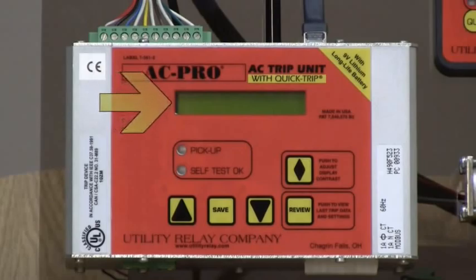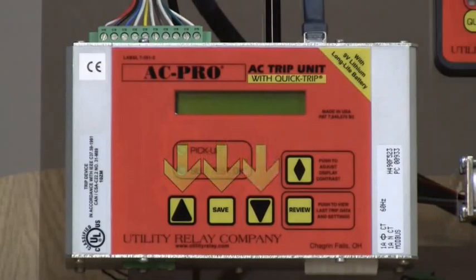The AC Pro has a 16-character liquid crystal display with a backlight. The contrast button is used to adjust the LCD contrast. Just push and hold the contrast button until the desired contrast is reached. When the contrast button is released, the contrast adjustment is saved. The review button is used to review the last trip data, the trip counter, and the AC Pro settings. The up button, save button, and down button are only active during the programming of the AC Pro.